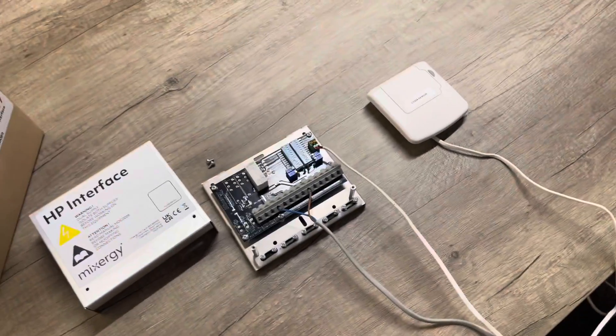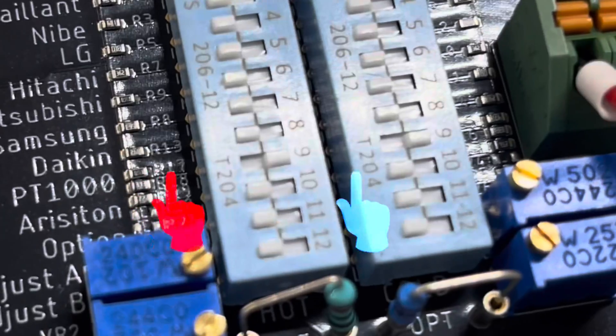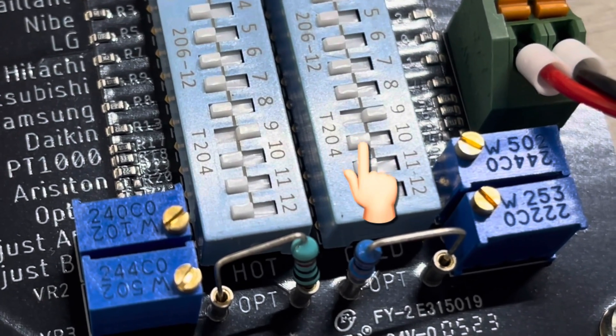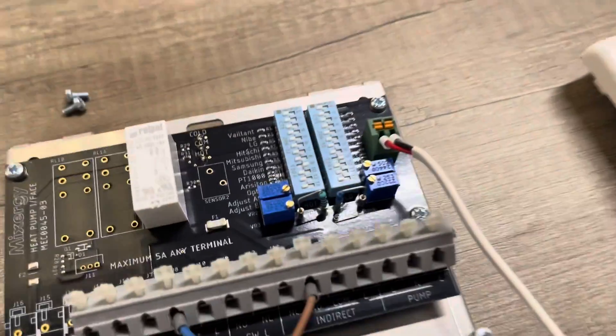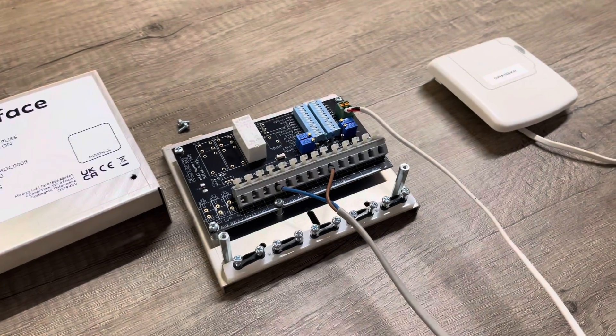So that is the heat pump interface working with the EVO home system. One other technical detail: we were using dip switch number nine to achieve the temperature swings between the cold and the hot resistor banks. So if you are using the heat pump interface, you do need it on number nine, and then your EVO home system can be controlled perfectly using the Mixergy cylinder.